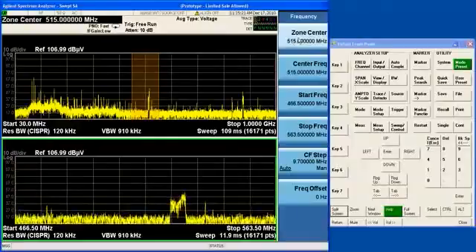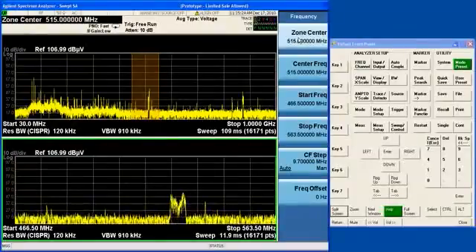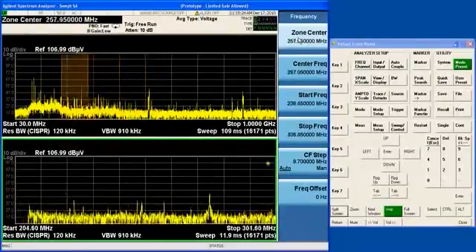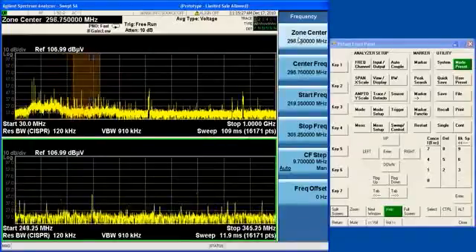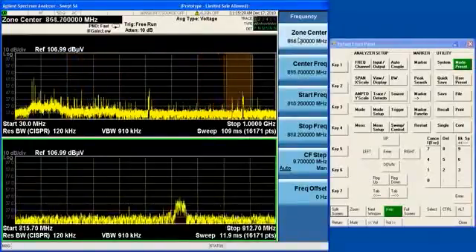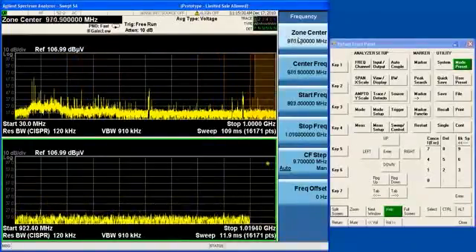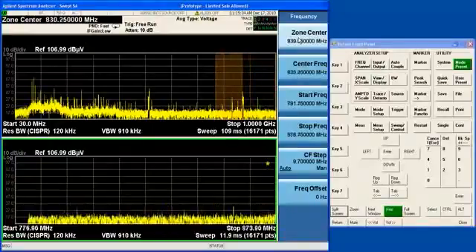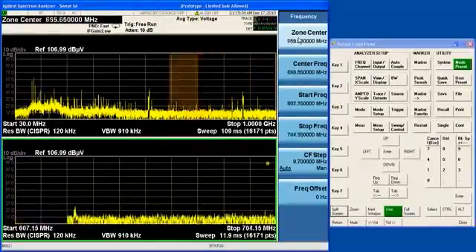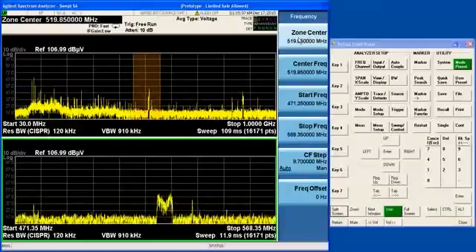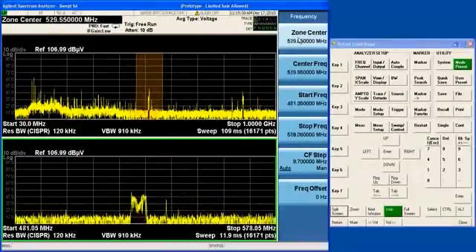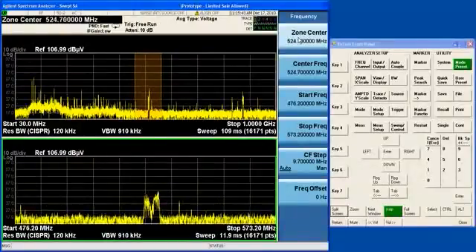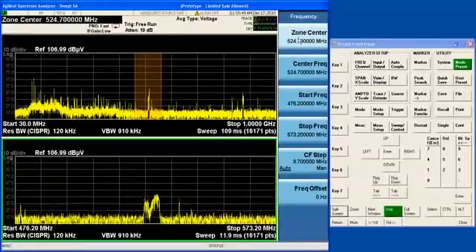You can move the Zone around by adjusting the Zone Center control. Now, the Zone by default is 10% of the display region in the upper window, so by moving it around, you can see that I've got the ability to zoom in on some of these signals that I can see in the upper window.